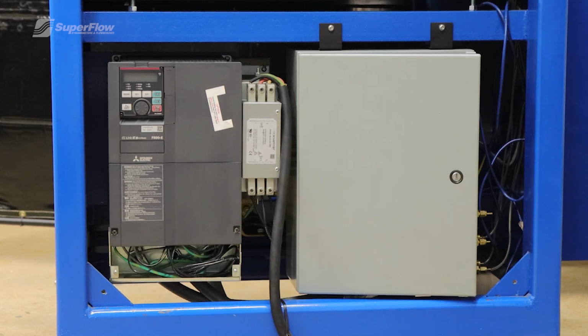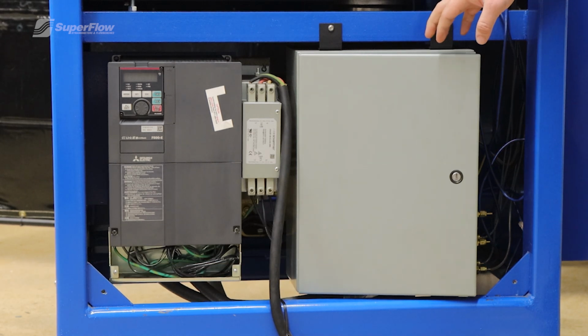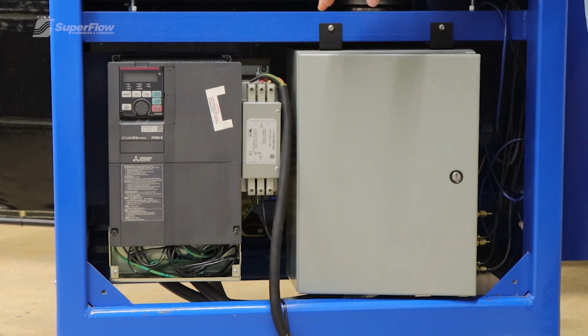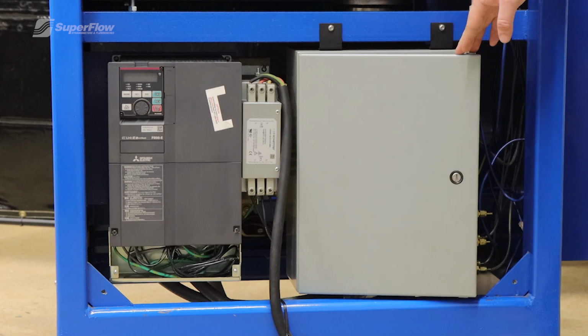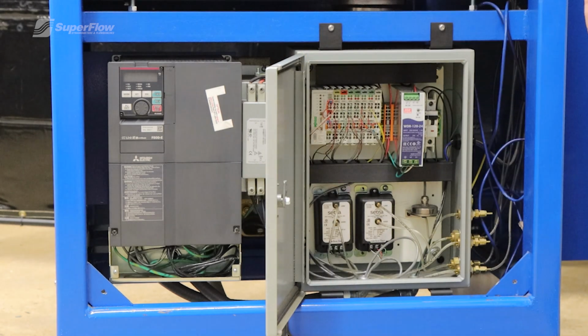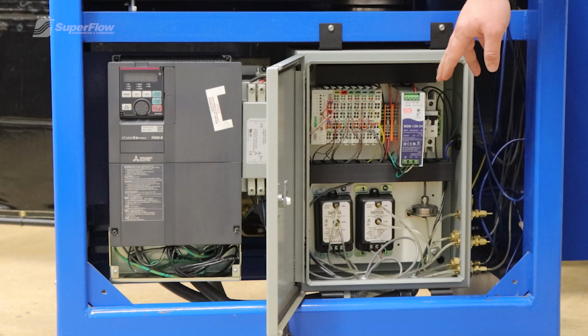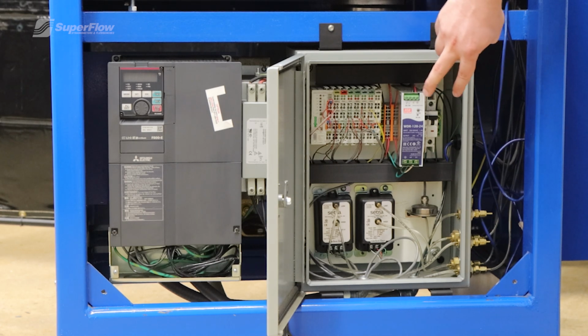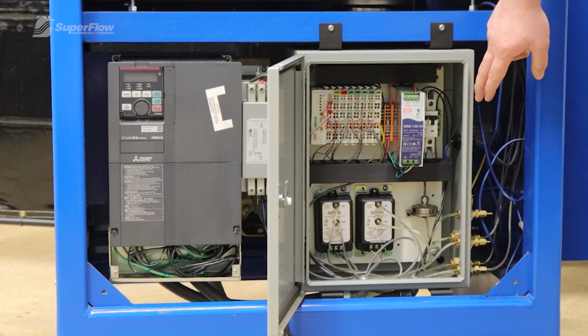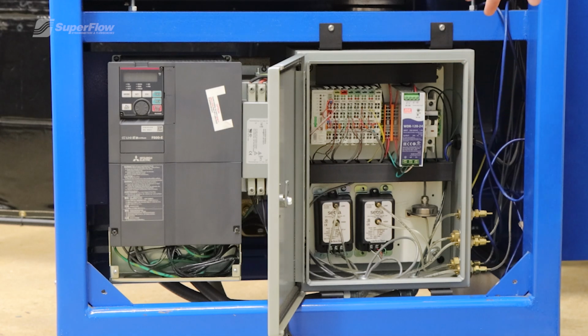As you see here, in the right-hand side, we have a control box, as well as the power input, and then a VFD to control our AC motor. Inside the control box here, we have a Wago PLC, a standard power supply, two pressure transducers, as well as a barometric pressure sensor. In addition to the Orifice calibration, the accuracy of the Orifice calibration is very dependent on the accuracy of these pressure transducers. To calibrate those, please refer to our 1020i flow bench manual.